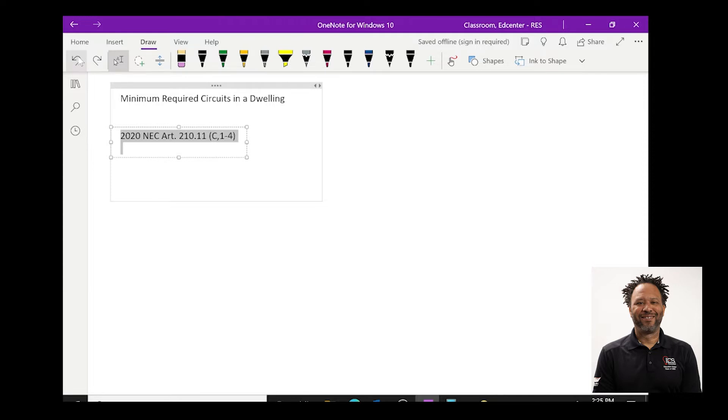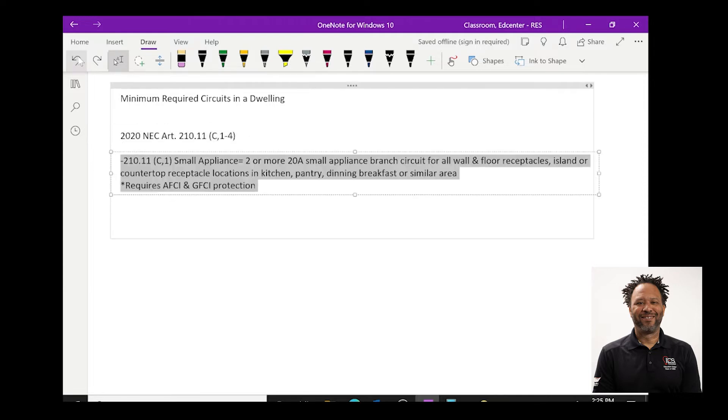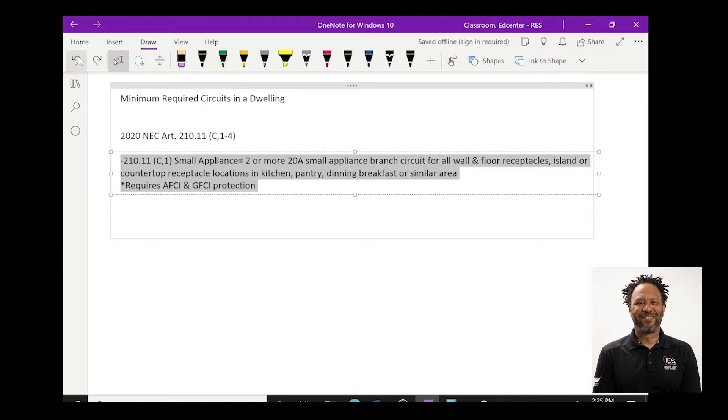210.11c1 lists the small appliance which states that two or more 20 amp small appliance branch circuits for all wall and floor receptacles, island or countertop receptacle locations in kitchen, pantry, dining, breakfast, or similar areas. These two circuits must be in the kitchen and they are also allowed to serve the dining and breakfast areas.